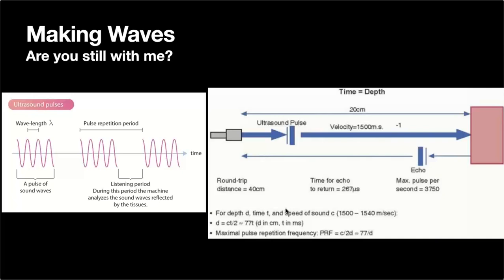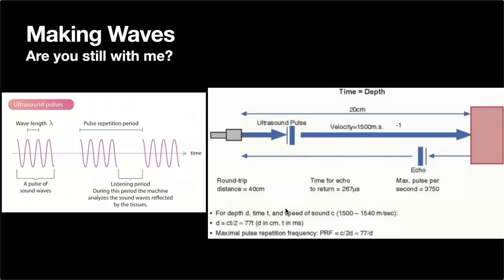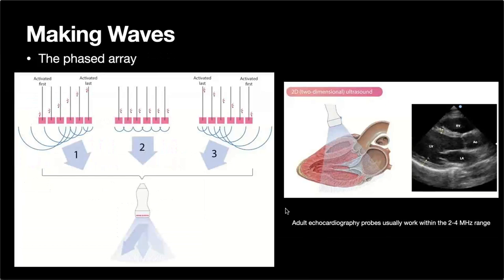There's a relationship between frequency and depth. High frequency and low wavelength means the ultrasound beams won't penetrate structures as deeply. Low frequency and high wavelength gives a longer near field and greater penetration. Frequency is intimately related to this near field distance. The machine is mostly listening, waiting to see how long the echo takes to return and then assessing the distance.